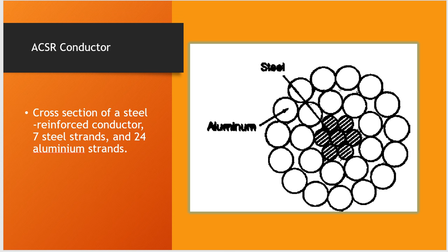After this we can see that the previous figure, that is figure 1, shows the cross sectional area of a typical steel reinforced aluminum cable, that is ACSR. The conductor that has been shown has 7 steel strands forming a central core, as I have told you, around which there are 2 outer layers of aluminum strands. There are 24 aluminum strands in the 2 outer layers. The conductor stranding is specified as 24 aluminum, 7 steel. Basically this specification is about the conductor stranding.